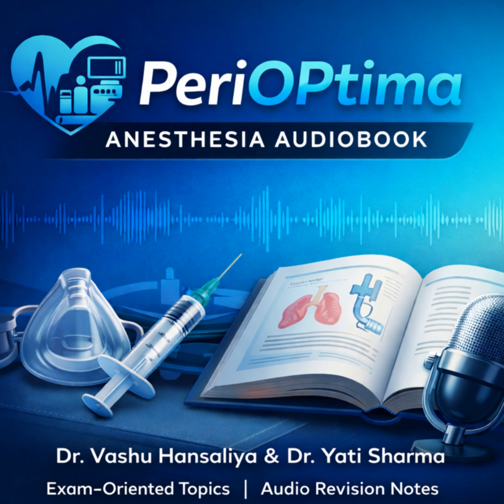Let's drill the numbers. Oxygen first. What do we need to know? Okay, the oxygen cylinder body is made of molybdenum steel. This specific alloy is used to handle that immense pressure while keeping the weight manageable so you can actually lift it. And its capacity? For an E-type cylinder, the internal water capacity is roughly 4.7 liters, which, when filled, translates to about 660 to 680 liters of gaseous oxygen. And the pressure, when full, is, as we said, roughly 2,000 psi.